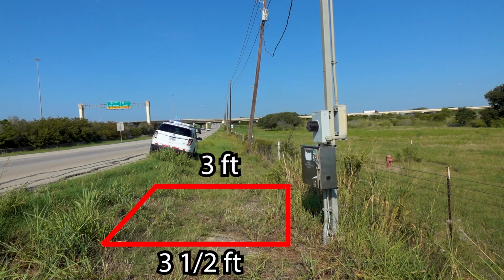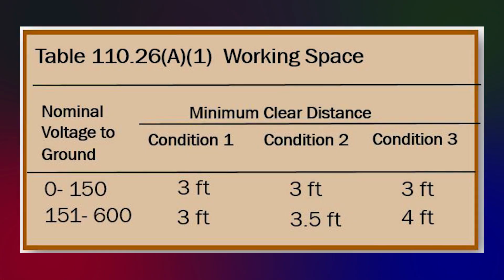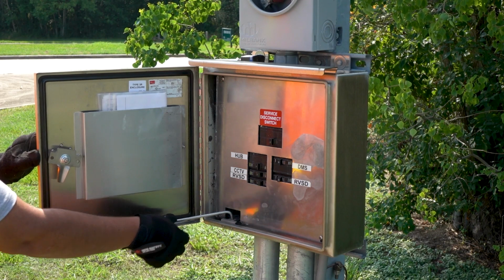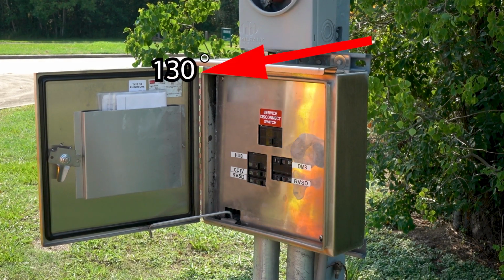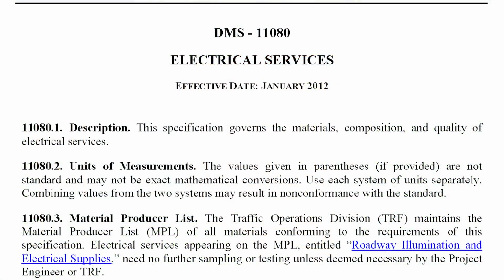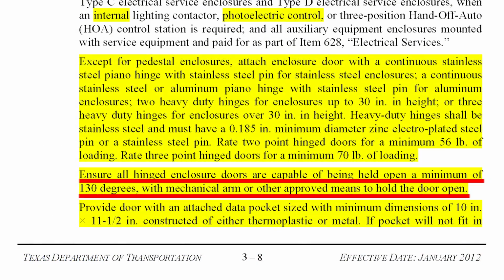The inspector will need to confirm that the clear working space in front of the service required by the NEC has been provided, and that there are no obstructions in the work area in front of the service. The inspector should also confirm that the door can be opened to at least a 130-degree angle and is provided with a mechanical means to keep the door held open, as required by DMS 11080 Electrical Services.